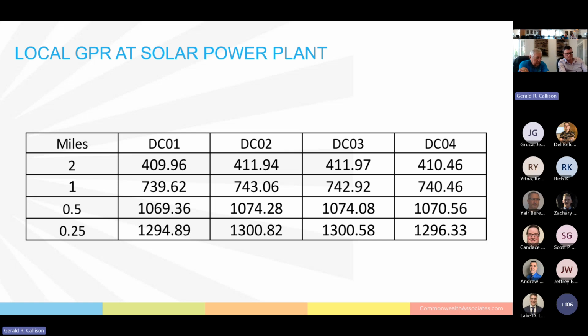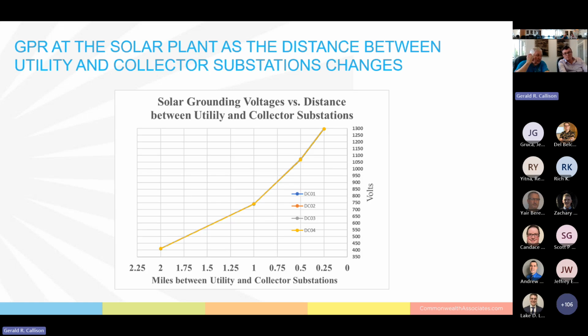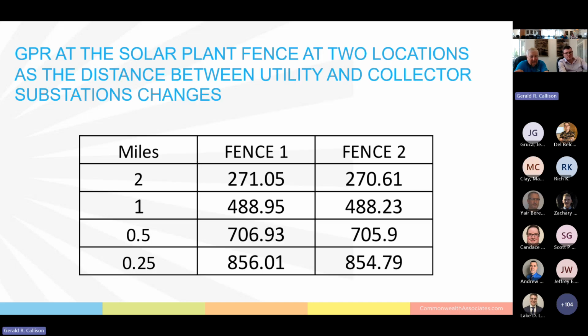So if we look at that on a graph, for us folks that are more visual, you can see that as you move the utility closer to the collector station, there is an impact on the collector station, and the voltages basically go up in the solar plant from about 410 up to around 1300 volts. So if we look at what's happening with the fence, it follows the same trend. The closer you get the utility substation to the collector station, the GPR in the solar plant goes up. And so on the fence at 2 miles, it's at approximately 270 volts, and at a quarter mile, it's up to about 850. So what's this have to do with the design?